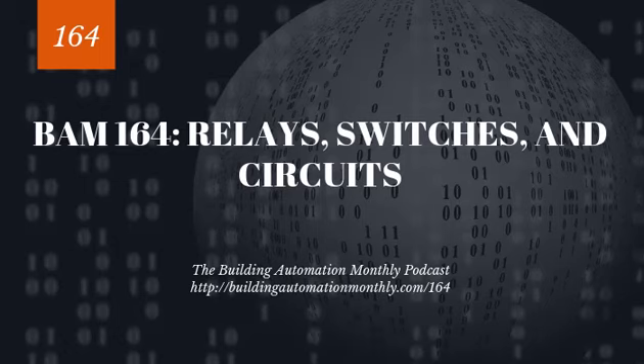Now, on top of that, you typically have a normally open set of contacts on all of these safeties. You'll run two wires through those normally open contacts, and that will be your status circuit. So you have a control circuit that I just described running through the normally closed, because as long as nothing's in alarm, that's going to be closed.